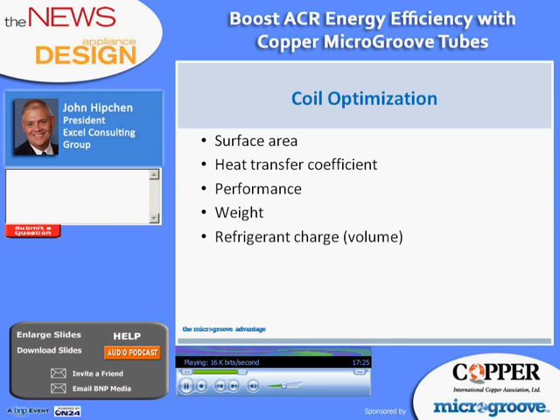The first three bullet points are all related. The amount of surface area is a direct result of the tube diameter, just as we discussed a few slides earlier. And the amount of surface area will have an effect on the heat transfer coefficient. The heat transfer coefficient, in turn, will drive the overall performance of the coil. The last two bullet points are important because the coil weight and refrigerant charge will have a big impact on the cost of the coil. So we will pay extra special attention to these numbers.